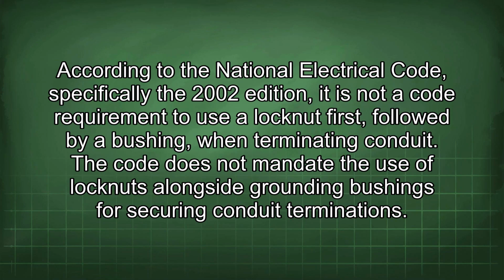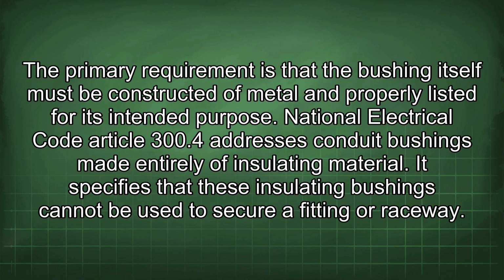According to the National Electrical Code, specifically the 2002 edition, it is not a code requirement to use a locknut first followed by a bushing when terminating conduit. The code does not mandate the use of locknuts alongside grounding bushings for securing conduit terminations. The primary requirement is that the bushing itself must be constructed of metal and properly listed for its intended purpose.